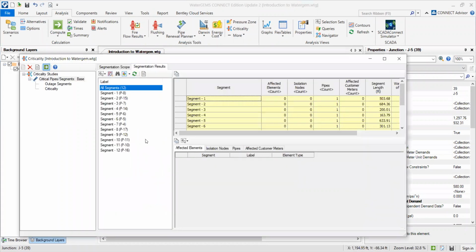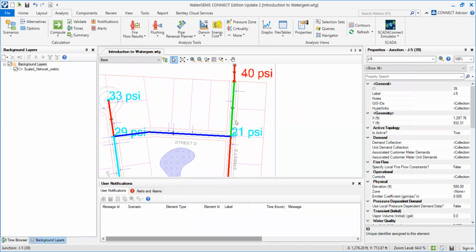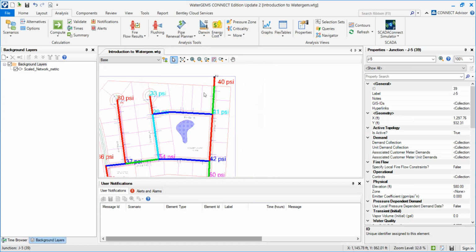So basically, in a water supply network, to determine the criticality of the network, we mostly use valves. If a failure occurs, for example, if I install here an isolation valve, or PRV, or PSV, and any failure in this pipe occurs, I can easily shut down this pipe by just closing the isolation valve, and I can reduce the part of the system affected, because the whole system is connected to this pipe.